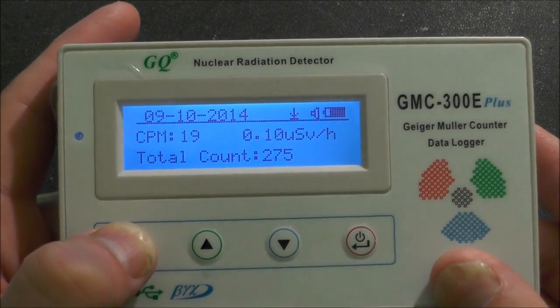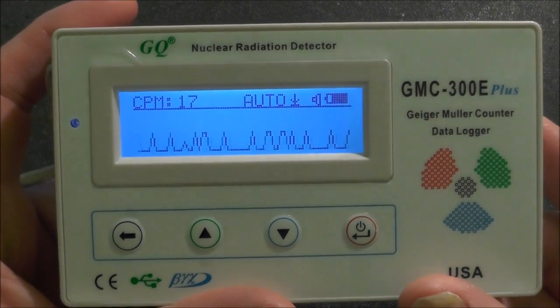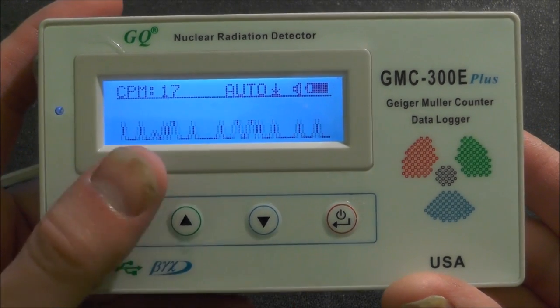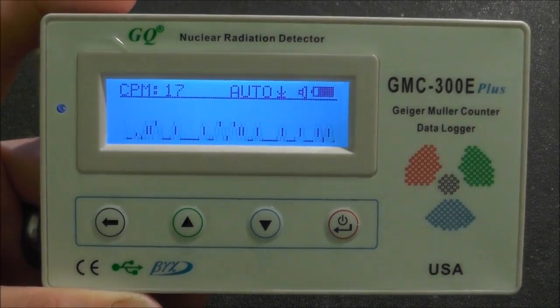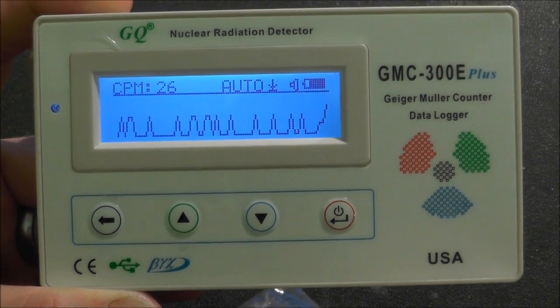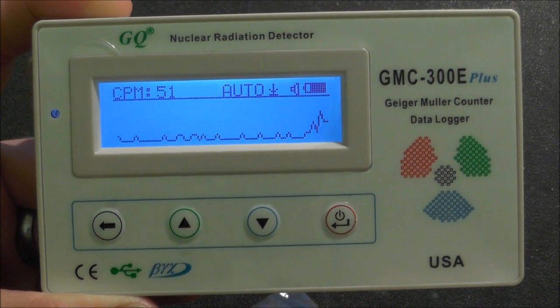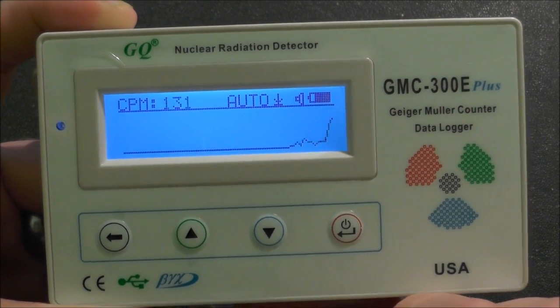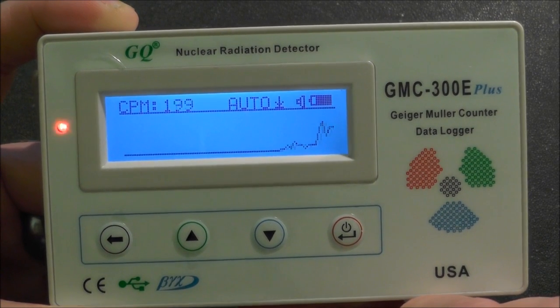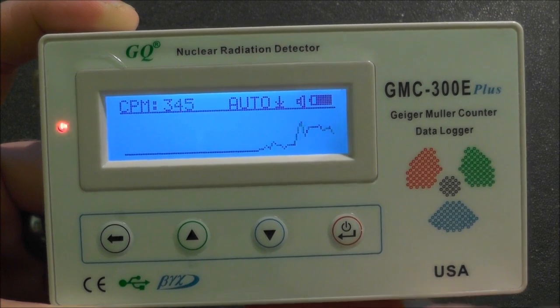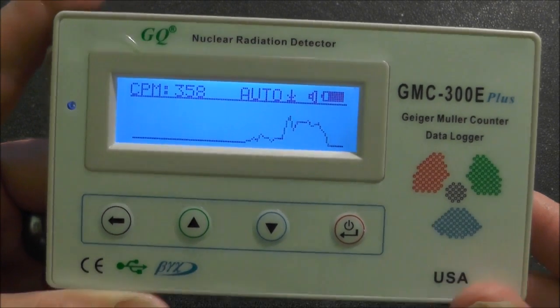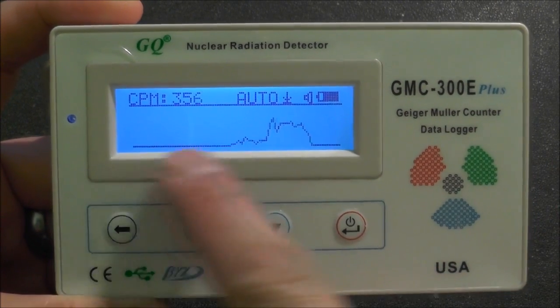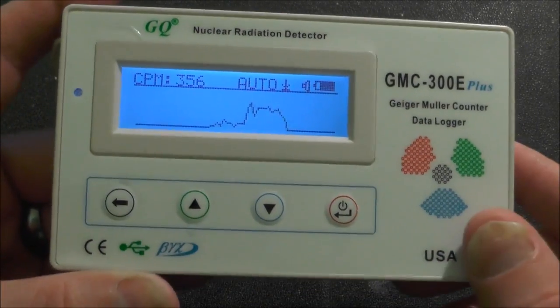The last display mode is the graphic mode, so this has a scrolling line chart of the last sixty seconds. Now it does auto scale, you can change it manually if you want to but it will auto scale normally. So if I put a few more counts on this then you can see it auto scaling there which is a nice feature, but you do only get the last sixty seconds. I haven't found any way to change it so it shows hours or days within a chart like that. I think they just expect you to just download it and put it into Excel to do that properly.